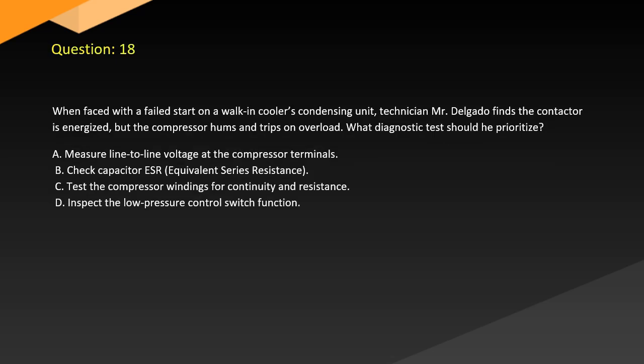Question 18. When faced with a failed start on a walk-in cooler's condensing unit, technician Mr. Delgado finds the contactor is energized but the compressor hums and trips on overload. What diagnostic test should he prioritize? A. Measure line-to-line voltage at the compressor terminals. B. Check capacitor ESR, equivalent series resistance. C. Test the compressor windings for continuity and resistance. D. Inspect the low-pressure control switch function.